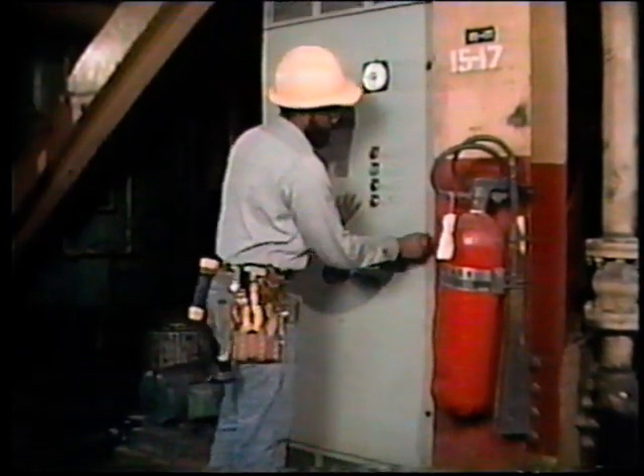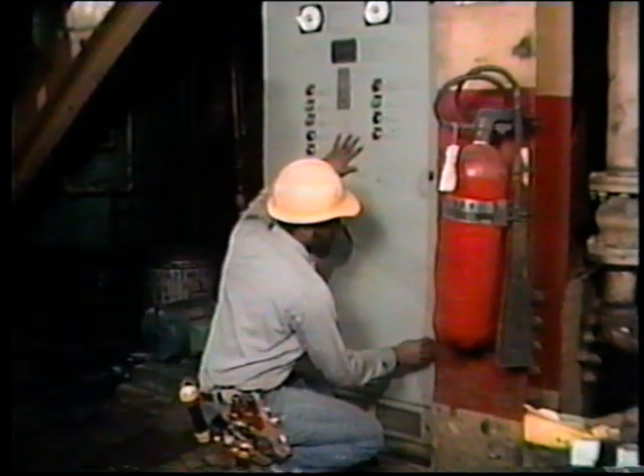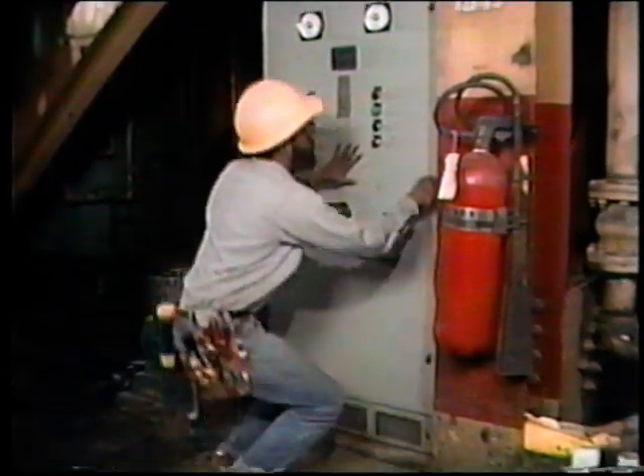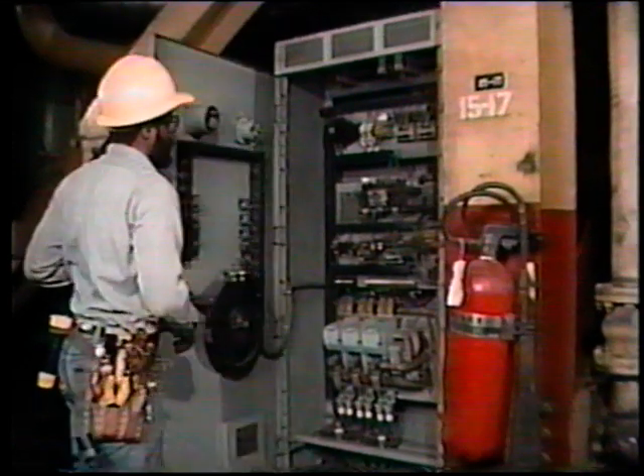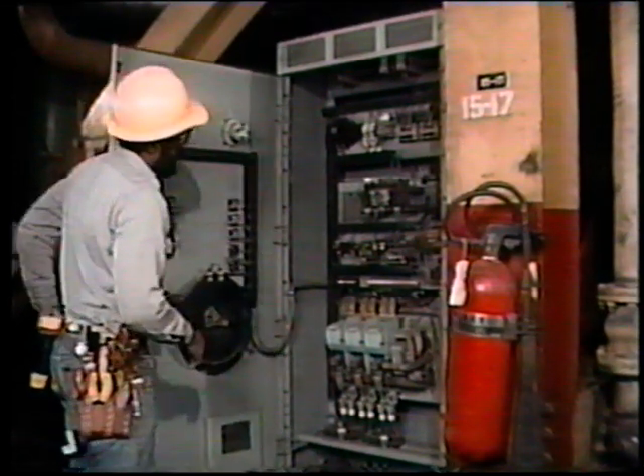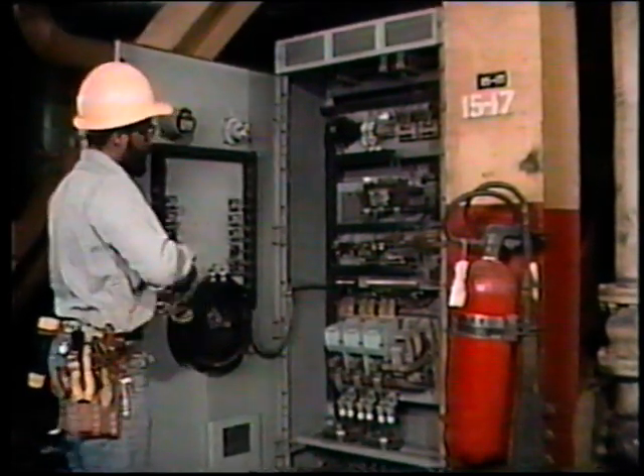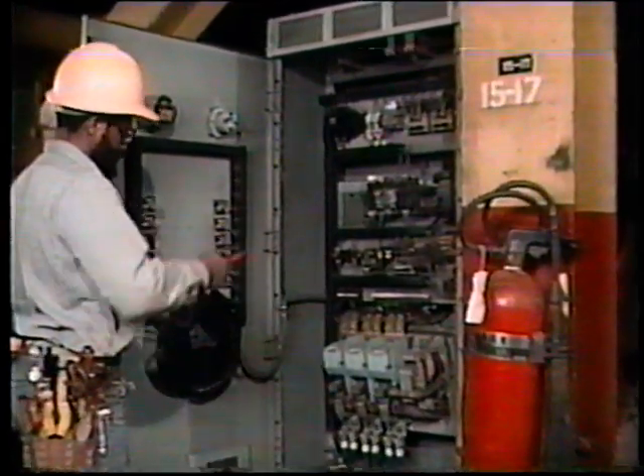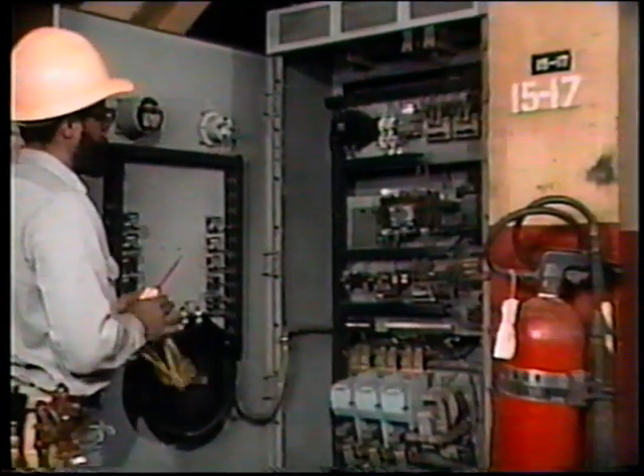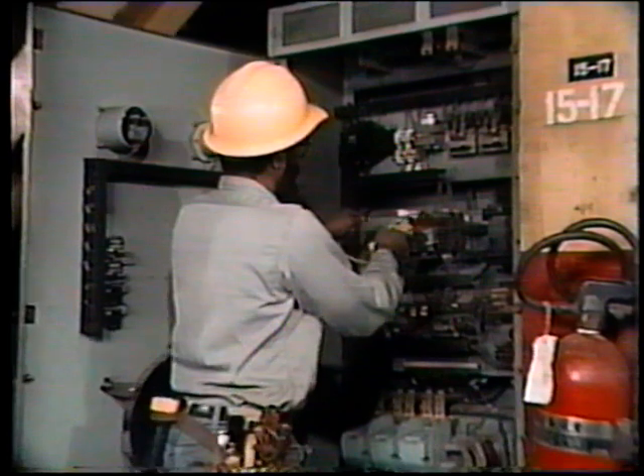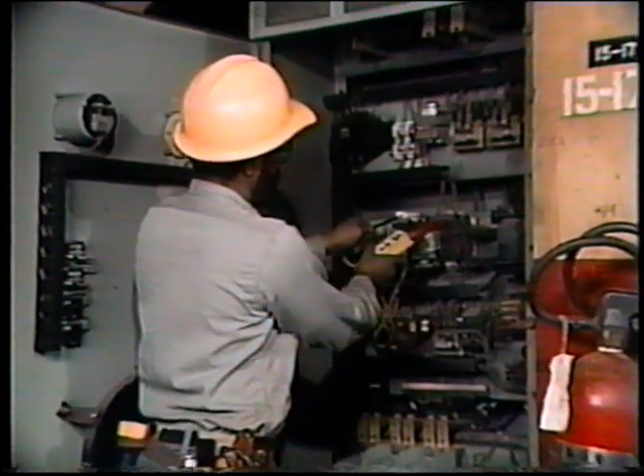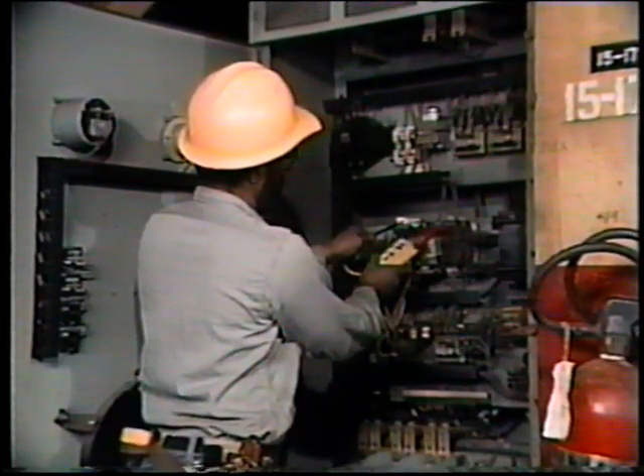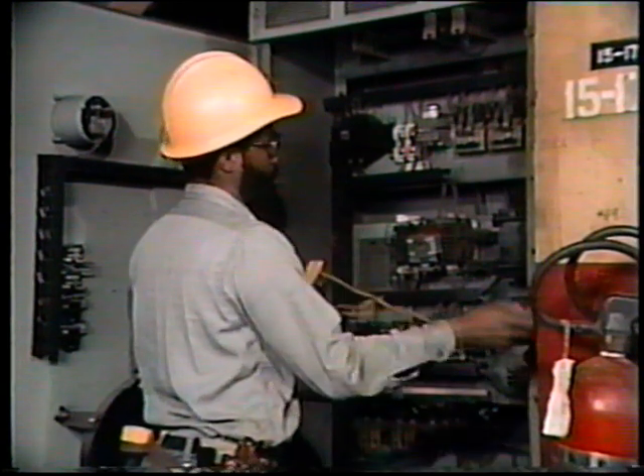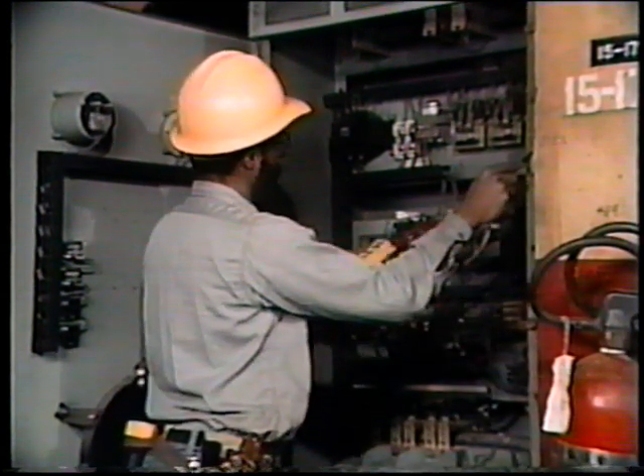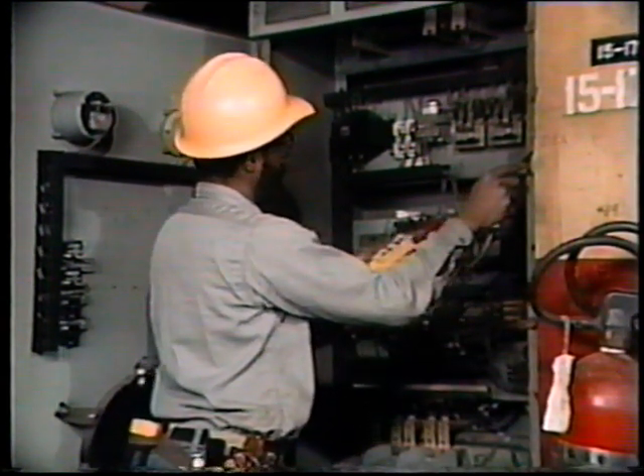Then the controller must be tested to make sure it's completely de-energized. A voltage tester, which has been checked for proper operation, is used to test the controller. The voltage tester probes are placed at each line of the DC power supply, and a reading is taken. The voltage tester should indicate that there is no power. Then each line is tested to ground. Again, there shouldn't be any indication of DC power.